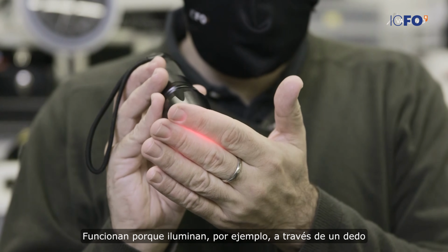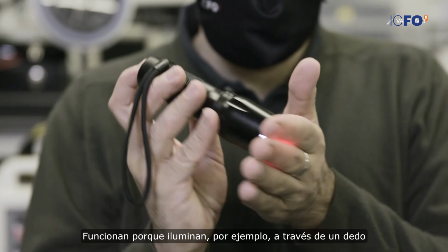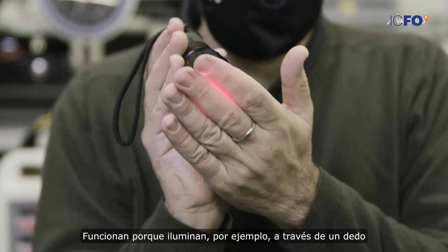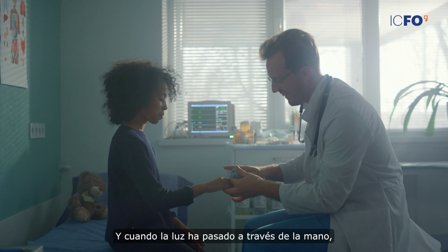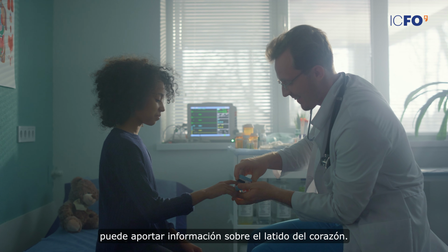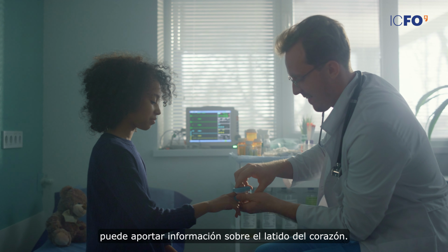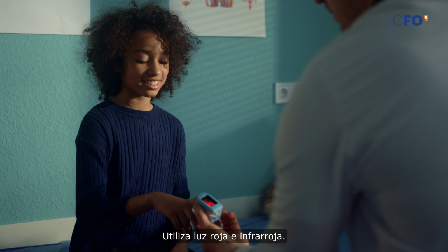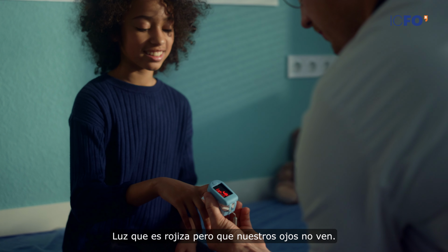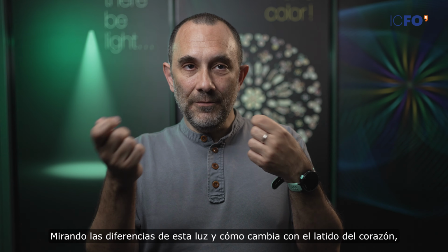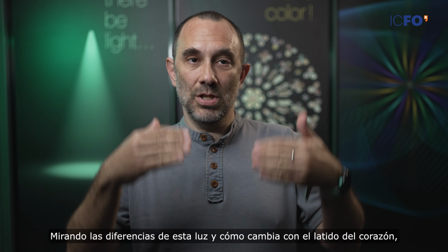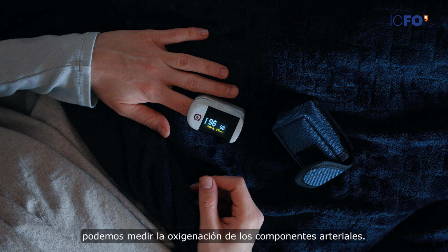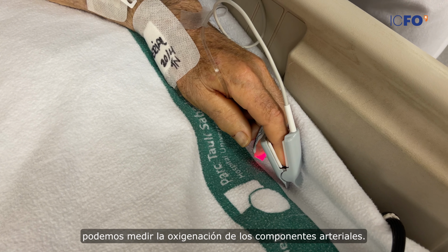How do they work? They work because they shine light through, for example, one's finger, as you saw on the screen, and when light goes through the hand, it can get your heartbeat out. It uses red and infrared light that is reddish but our eyes cannot see. By looking at the difference of these things and how they change with the heartbeat, it's able to get the oxygenation in the arterial components.